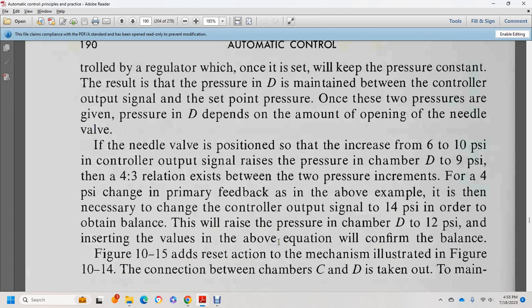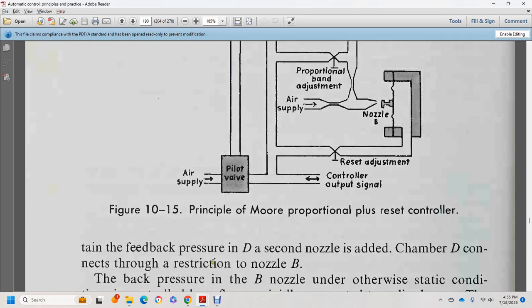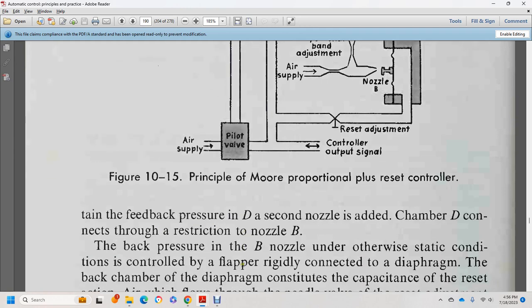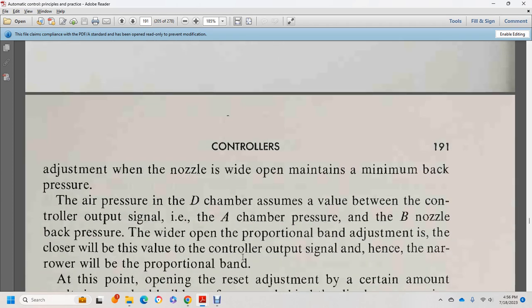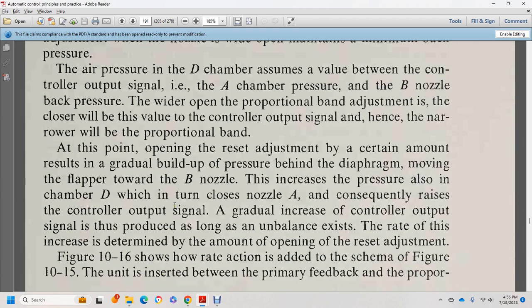If control output increases to 10 psi, pressure in chamber D rises to 9 psi in a 4-to-3 relation between the two pressures. With a 4 psi increment of primary feedback, the controller output signal changes to 14 psi to obtain balance, with pressure D at 12 psi. Inserting values into the equation confirms the balance. Figure 10-15 shows the reset action mechanism: the connection between chambers C and D is replaced by a second nozzle. The needle valve reset adjustment gradually moves the flapper toward the nozzle, increasing back pressure, closing the reset adjustment nozzle, and maintaining the air pressure in chamber D between the controller output and chamber A.